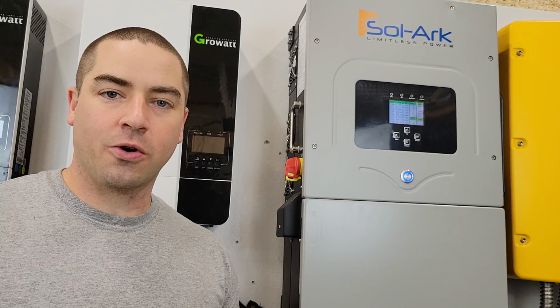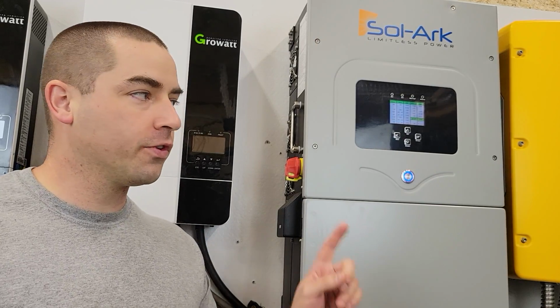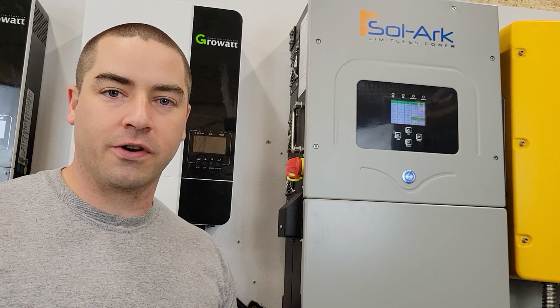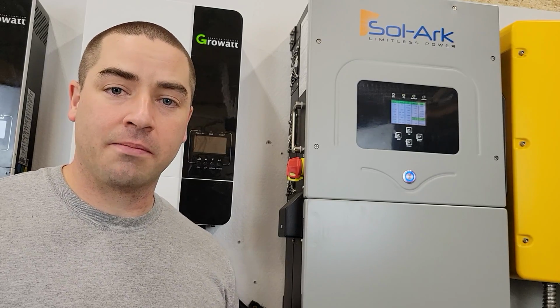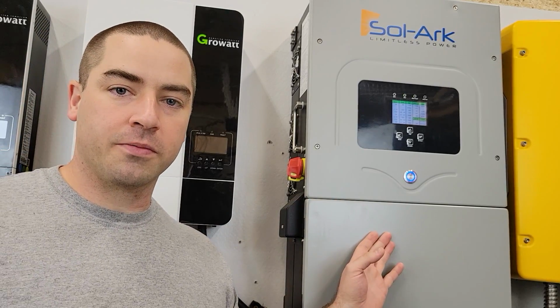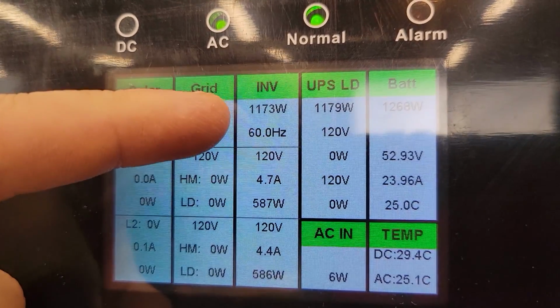We just switched the whole property, so the house and garage, over to running on the Sol-Ark inverter again. But this time we don't have the neutral from the inverter. We only have a neutral being provided from our auto transformer.